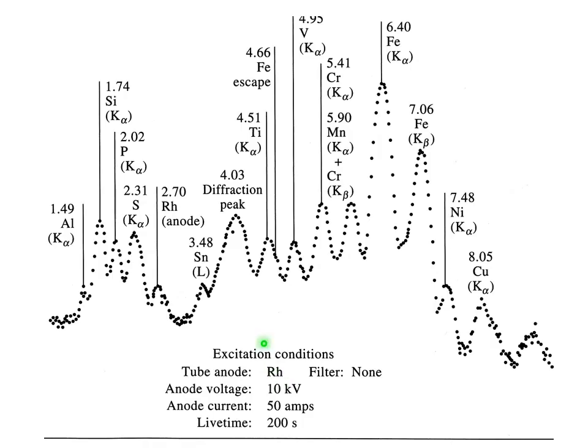By doing this you are getting spectrum like that. Peaks are not as sharp in our previous example but still can be separated easily. You can see peaks of different elements: silicon, phosphorus, sulfur, tin, titanium, and so on. You have a spectrum and that is how you can analyze your sample. This device can be made very small. You can make handheld x-ray fluorescence instrument. They are relatively inexpensive and they have wide usage for non-destructive analysis of wide range of samples.